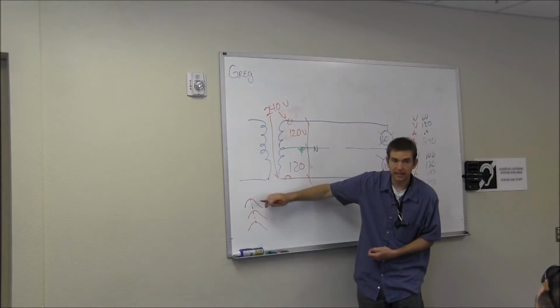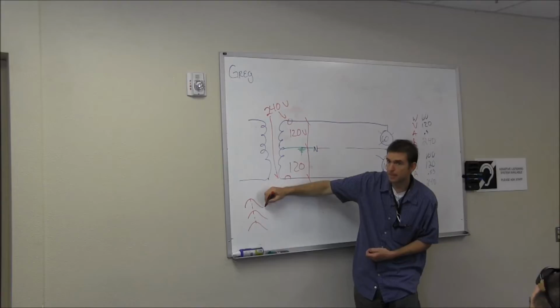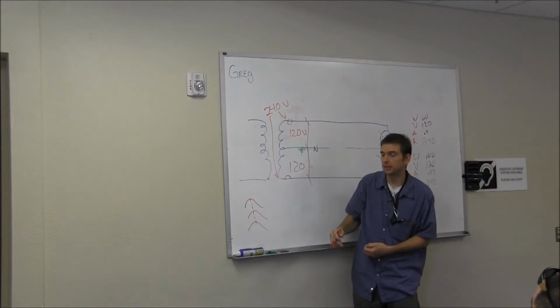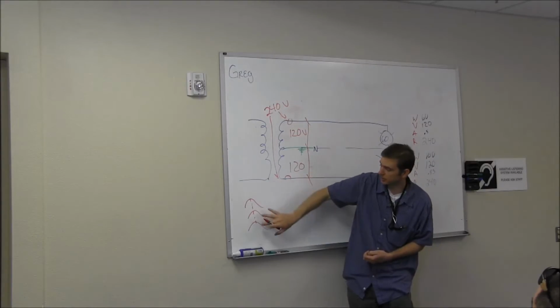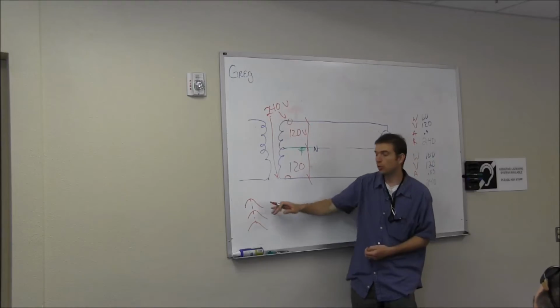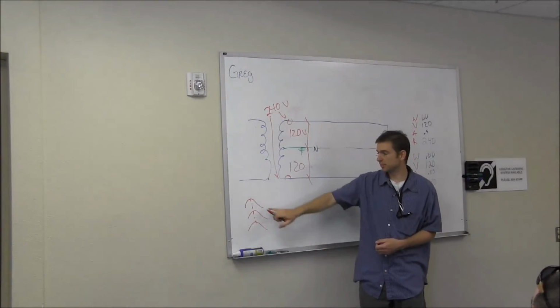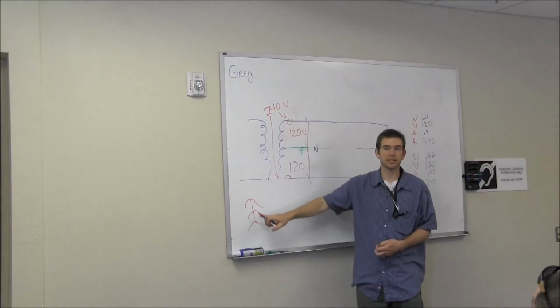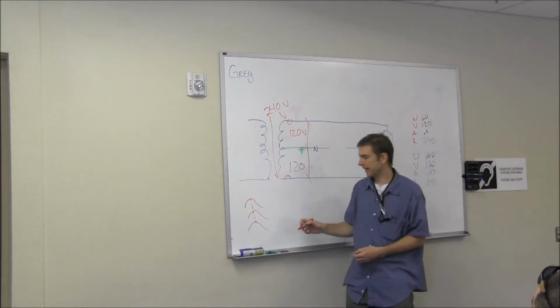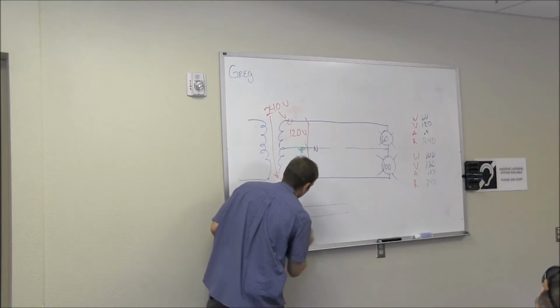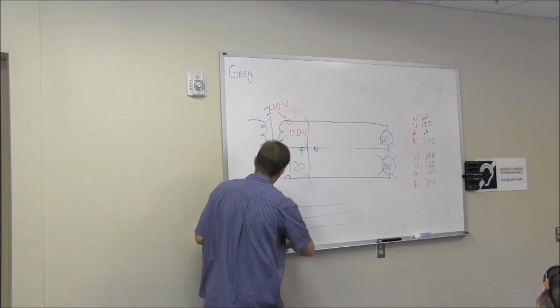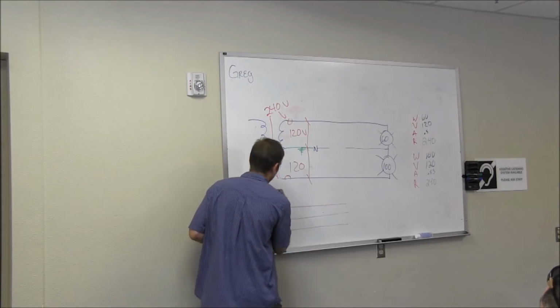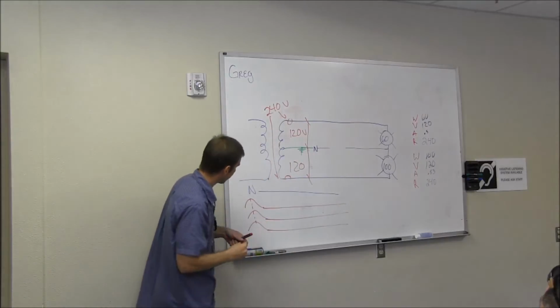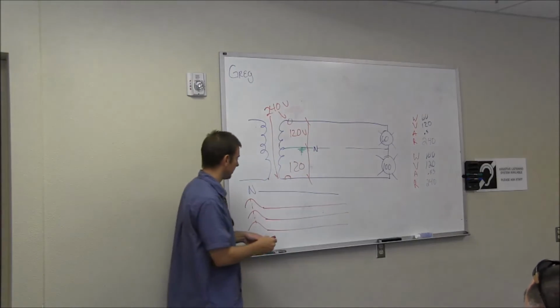With a bar? Yeah, mechanically tied together. So if this breaker trips, it's going to trip the other 2 as well. All 3. And if you go in there and you want to turn off this breaker, you're physically going to turn off these other 2 as well. And that's important because you have 1, 2, 3 wires going back in the field, and I'll use the blue for our neutral. We have a neutral going back. That neutral for that 3-pole breaker, let's say this is feeding a receptacle.